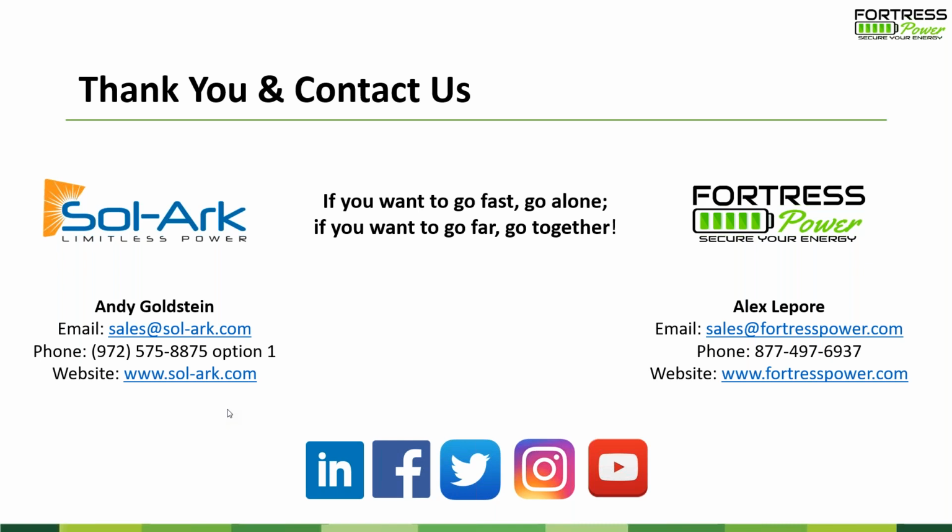Okay. Phil is asking, can my off-grid home customer use a Sol Ark 12K with a 10 kilowatt hour Fortress LiFePO battery as the prime power system? And is there a recommended backup generator kilowatt size which would be optimized for the solar converter? I'll take this question. The short answer is yes. The longer answer is, what are we looking to power? If we understand what the customer needs to power, then we can calculate the amount of storage, if 10 kilowatt hours is sufficient. If it's double that, maybe we need to go with the eVault instead of the eFlex or the LFP10. We just need to look at that.